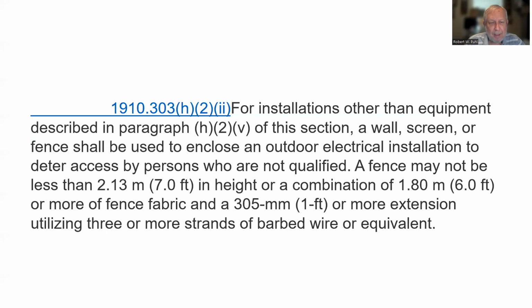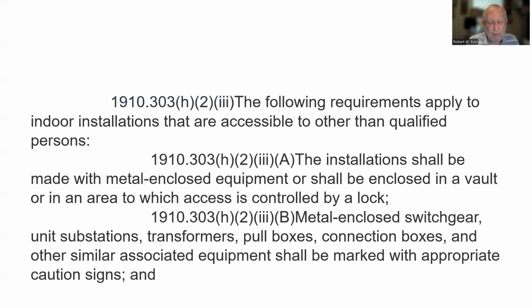A fence may not be less than 7 feet in height, or a combination of 6 feet or more of fence fabric and a 1 foot or more extension using 3 or more strands of barbed wire or equivalent. You got an electrical thing outside. You really want to make sure nobody gets around, messes around with it, for their own safety as well as just for the security of the facility.